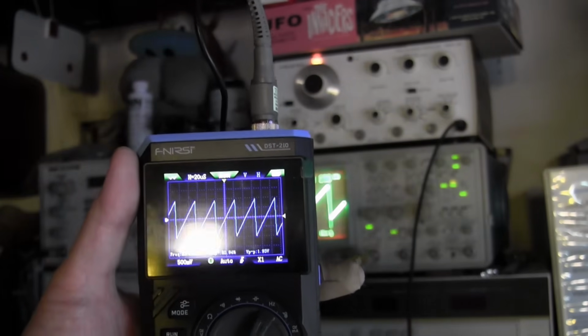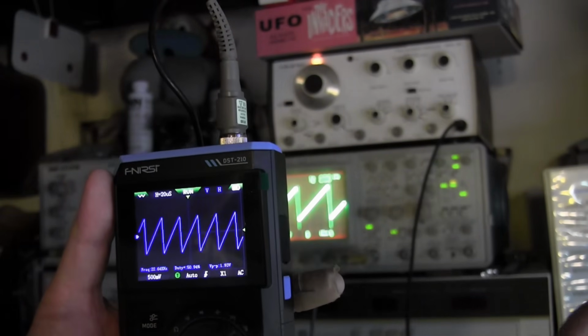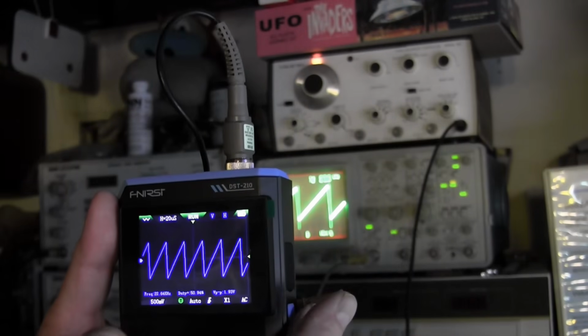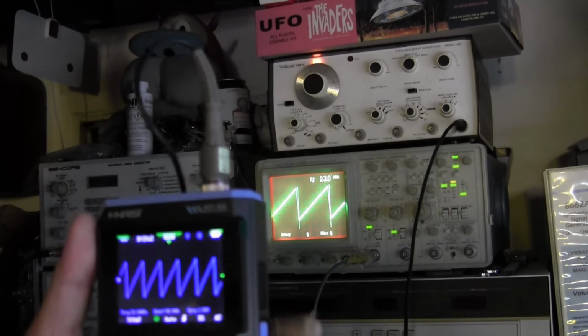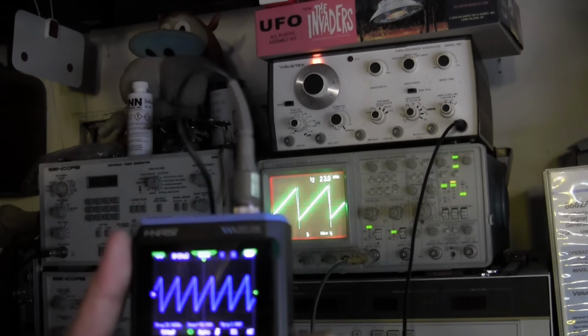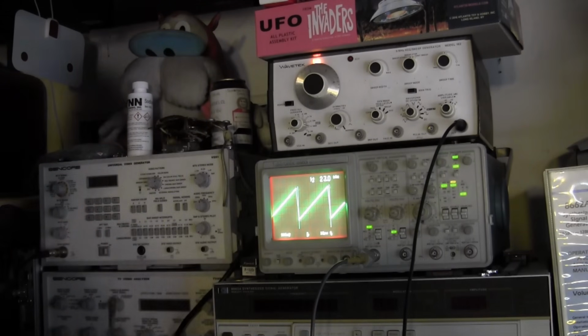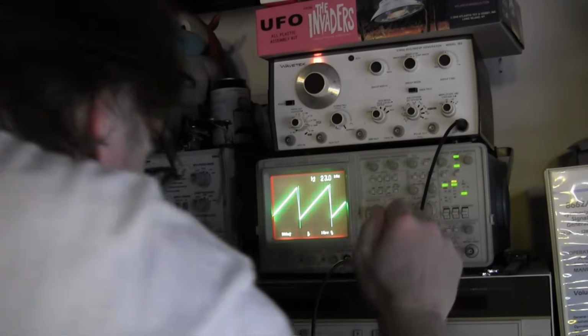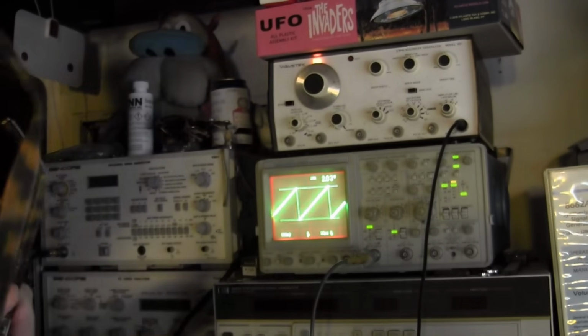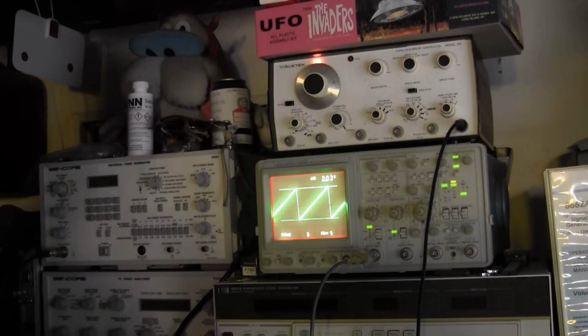Anyways, you should always use ×10 mode because it increases the input impedance sensitivity of the device, and also how much voltage you can put into it. So it says it's about 1.94 volts. Let's see what the Tektronix has to say. I'll put that in Delta V mode and do the same thing about there and about there and about 2 volts. So they're within, I don't know, I'm not going to do the math, but they're within a few percent of each other. So for the kind of work I'm doing, that's plenty accurate.